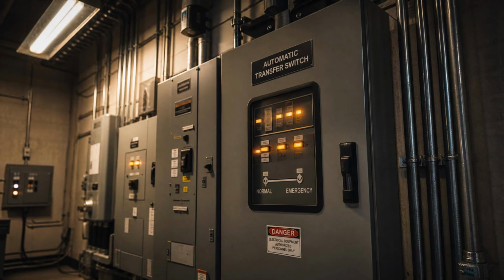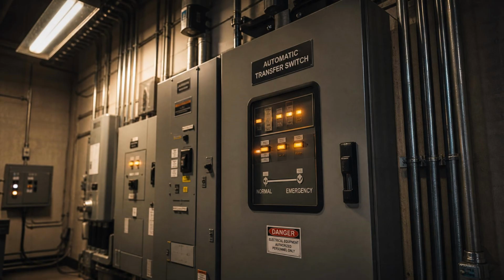First, the transfer switch receives the signal and confirms what it is being told. The normal source has been lost or has degraded below the threshold at which it can reliably serve the building's loads. This confirmation is not instantaneous. There is a brief, intentional delay built into the logic, a moment of measured waiting that serves a purpose. It ensures that a very brief disturbance does not trigger a full transfer unnecessarily. But if the disturbance persists, if the signal continues, if the normal source remains unsuitable, the transfer switch proceeds. It initiates the start signal for the emergency generator, and then it waits.